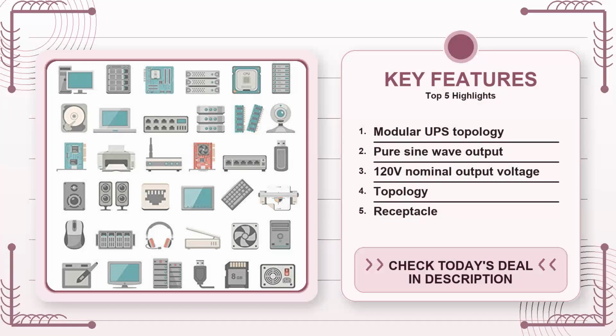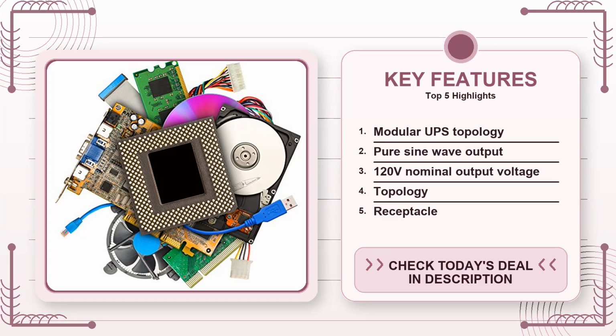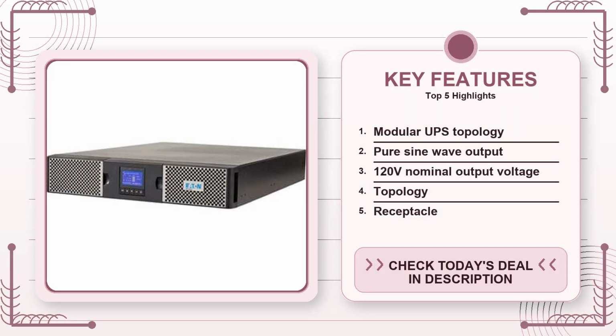That stability comes at a price, though. Double conversion draws a bit more from the batteries during an outage, which in turn reduces the total runtime compared to a line interactive UPS of the same VA rating. If you prioritize maximum backup minutes over absolute power quality, a line interactive model might give you a few extra minutes of runtime for the same price.